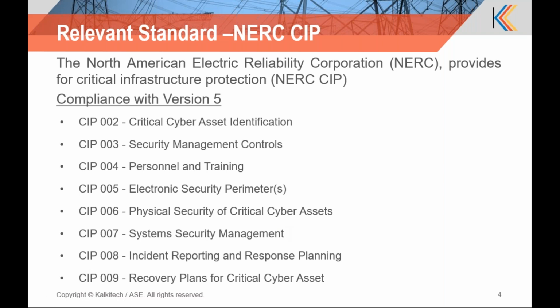is its management and control, what is the mechanism when there is a problem with cyber security, a vulnerability detected, how to report the system, what is the recovery standard. Everything is dealt in the NERC Critical Infrastructure Protection standard, and the standard to which we conform is version number 5, and the major thing applicable for the IED, that is substation environment devices, is Electronic Security Perimeters CIP 005 version 5. So that is a standard which mostly deals with our equipment security.